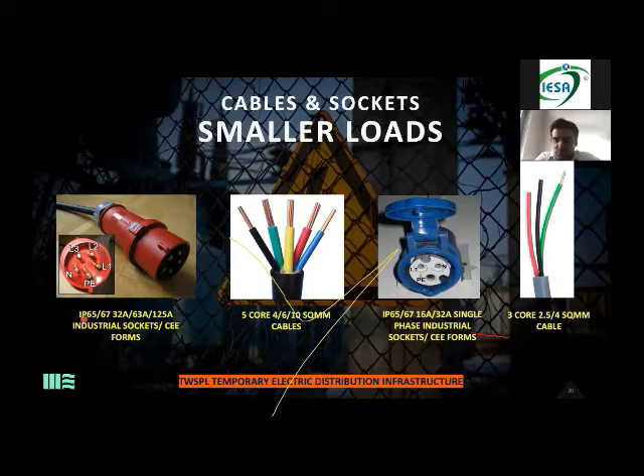Again, as I've written over here, these sockets only come in IP65 and IP67. Most of the time these sockets can be used for maybe your AC distribution, or for an outdoor show if you're doing one. As soon as you start using these IP65 and IP67 sockets, the loose wires on site, or somebody taping underneath your carpets, gets avoided immediately, because it becomes a plug and play system. These sockets come in 32 amps and 63 amps. We've already spoken that the unit of current is amps. So they come in 3 forms, 32, 63 and 125 for the 3 phase. If you want to buy single phase, they come in 16 amps and 32. There are other things also, but these are the most widely used sockets all over the world, and in India as well.